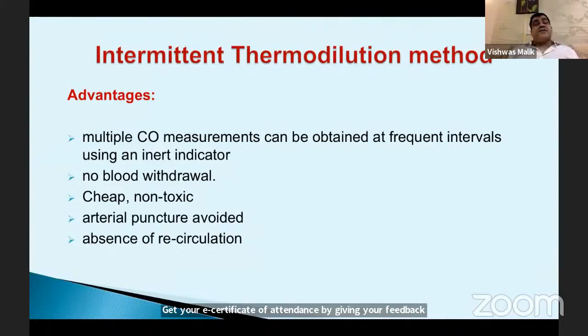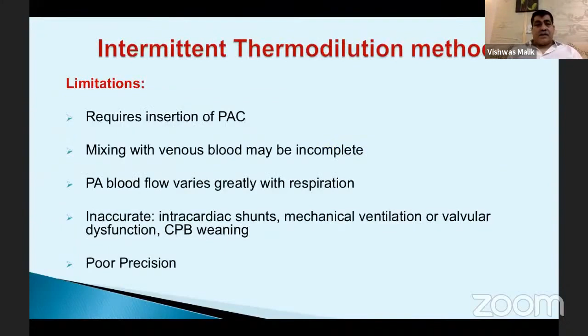We already said that it is inaccurate in the presence of intracardiac shunts, mechanical ventilation, valvular dysfunction, or during CPB weaning, and it is difficult to reproduce the same values. That's why we said that if the fluctuation within the two values is more than 10%, this means the cardiac output measurement is unreliable. So how do we address the loopholes of the intermittent thermodilution methods?